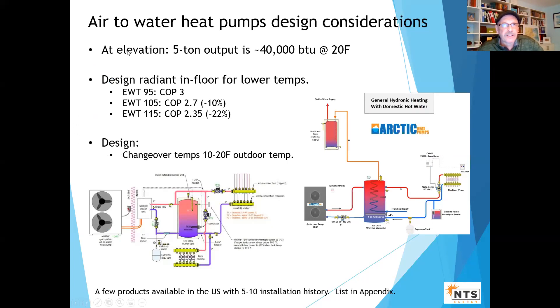For air-to-water heat pumps: a single unit derated is going to be at about 3.5 tons. The design of the radiant in-floor is even more critical here than with boilers — these are entering water temperatures, and for about every 10 degrees higher your floor requires, you lose about 10% capability and COP. So design for as low water temperatures as possible. Options include mono-block — where the refrigerant cycles outdoors and you run glycol/water into the buffer tank — and split units, with no refrigerant handling required for the mono-block configuration.